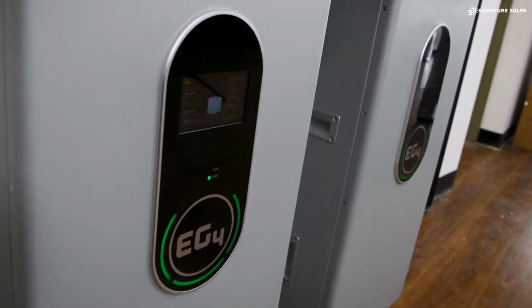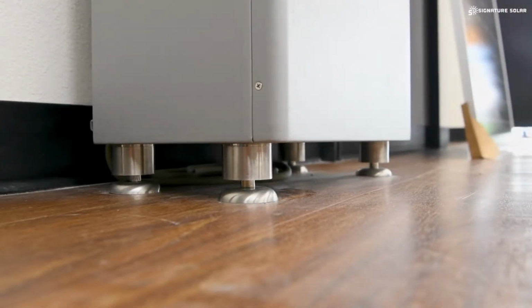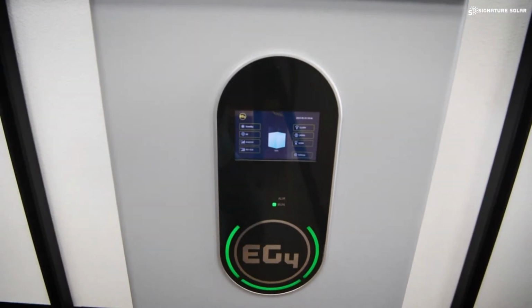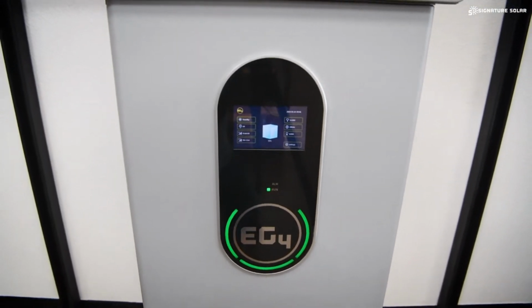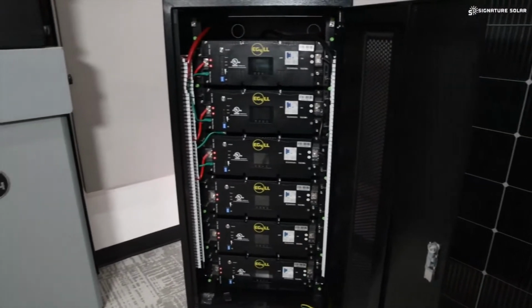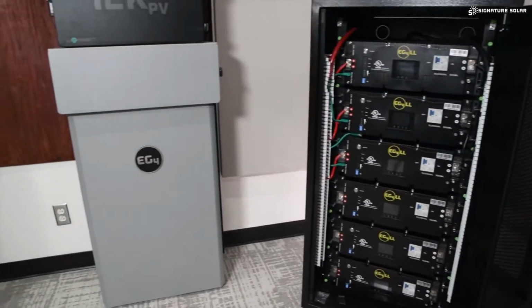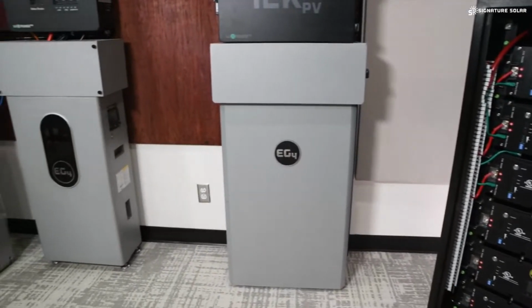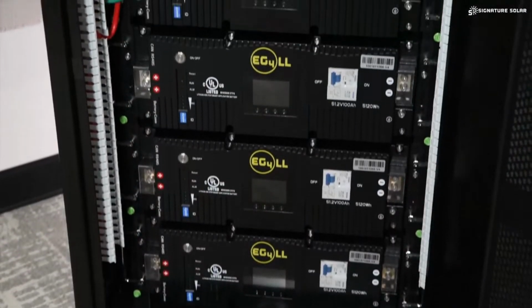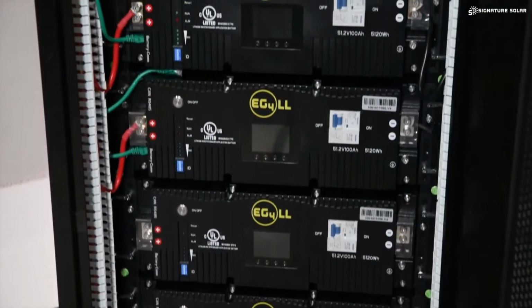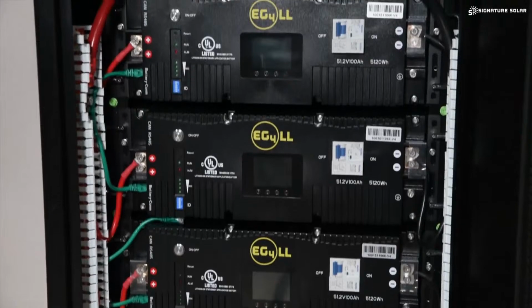Even when the BMS won't stay on and allow it to charge, it will let through a very small amount of amperage, what we call trickle charging. So you can get a separate charger and trickle charge it to bring it back to life. A lot of the time you can't do that with the inverter because it's a safety feature — an inverter wants to see 48 volts or close to it before it sends much amperage, just to be safe. So you often need an external charger to bring it back to life. But sometimes you can have it all set up ready to charge as you turn the battery on, and as soon as you turn the BMS on, if it's not drawing off the cells but gets an external charge instead, it will come to life. So you can do it either way.